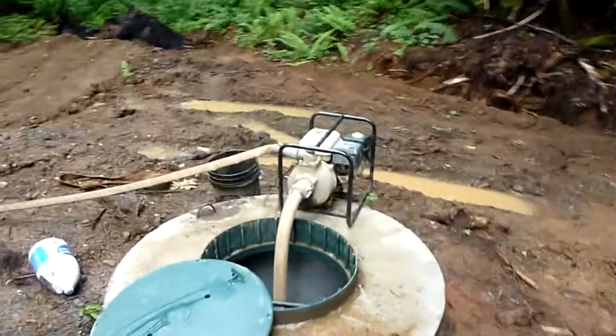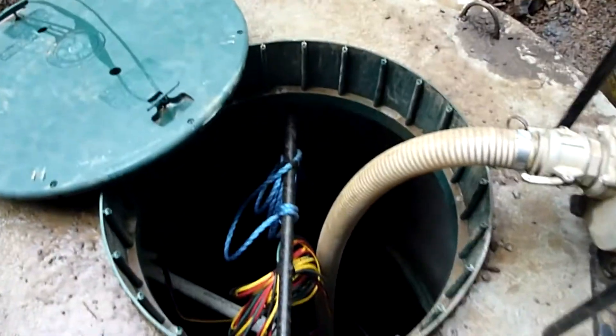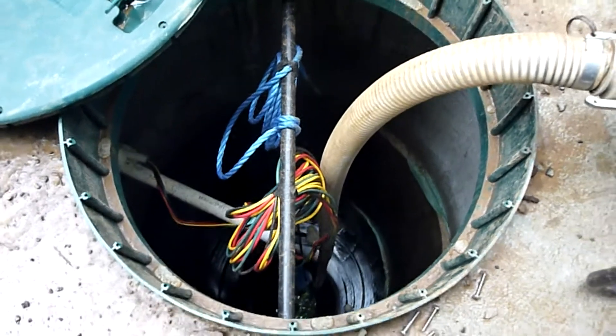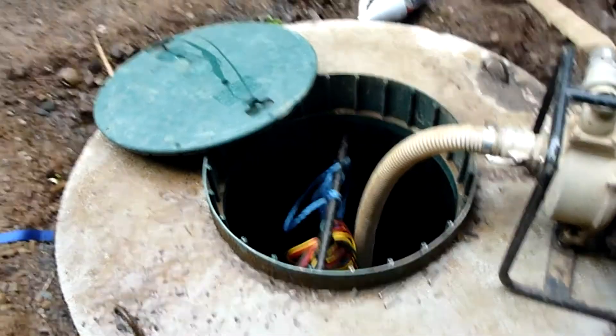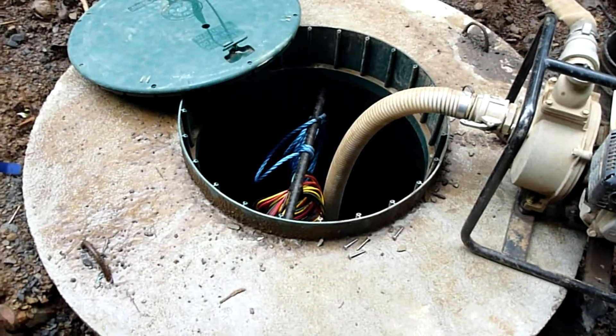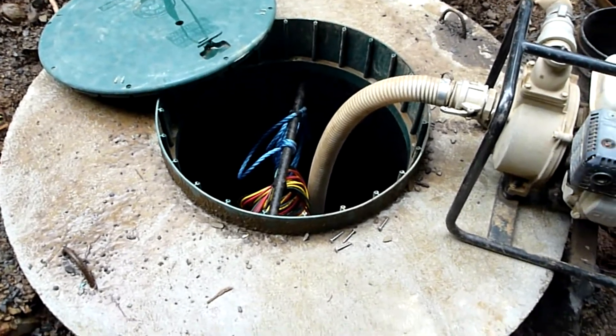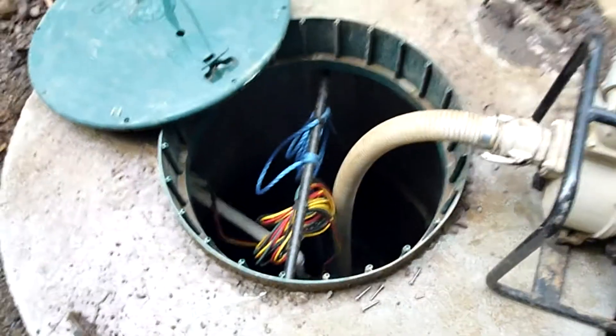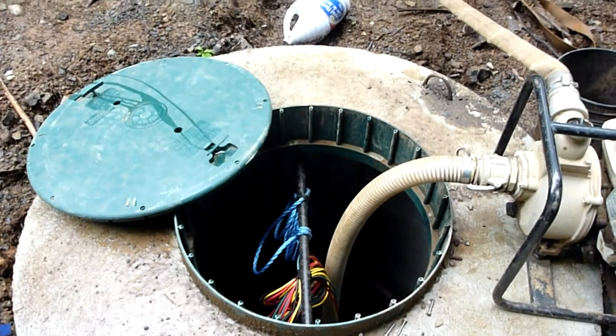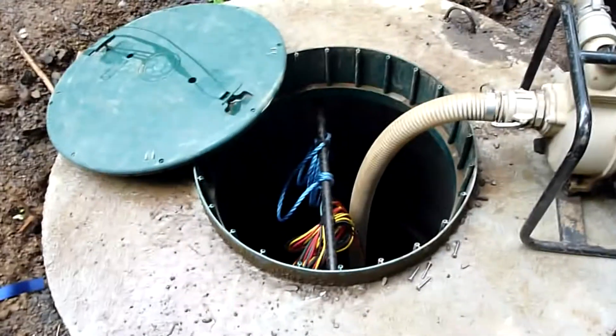Back at the well - this past week we've had a little bit of time to put some work in. We pumped the well right dry down to the bottom as far as we could get it, and dumped two and a half gallons of bleach in there. We filled water back in to push the bleach out into the other two underground buried towers and into the annular space, to make sure we get good treatment throughout and kill anything hiding in the rocks or in the other towers. We pumped her dry and that's where we're at. It filled up a little bit overnight, so I'm going to pump her right dry again and throw in a couple more gallons of bleach - just to do it a second time and make sure any bacteria, coliforms, or anything else is killed off.